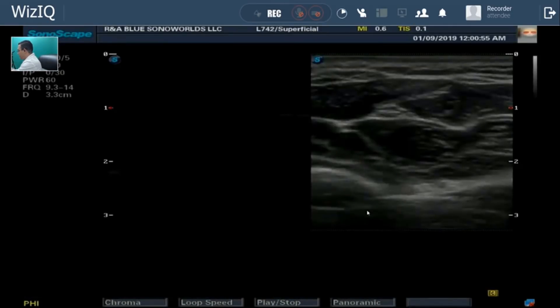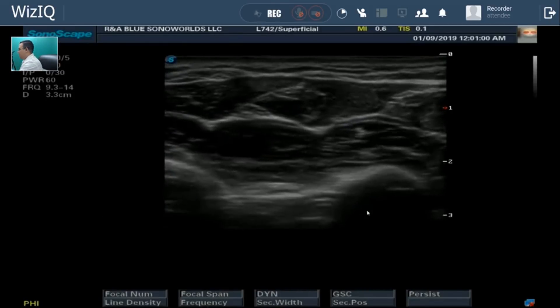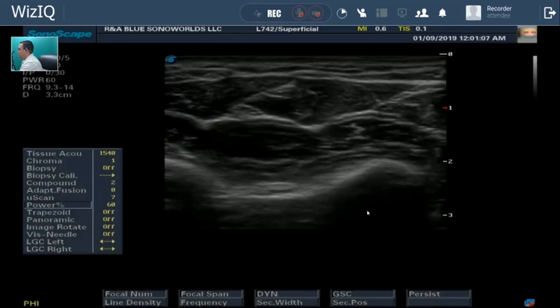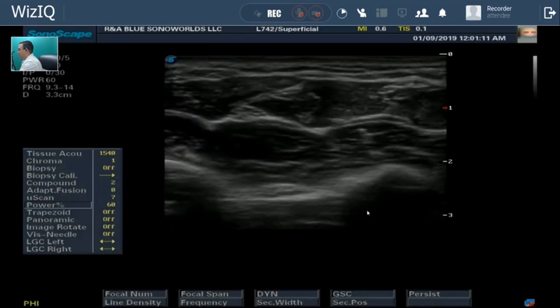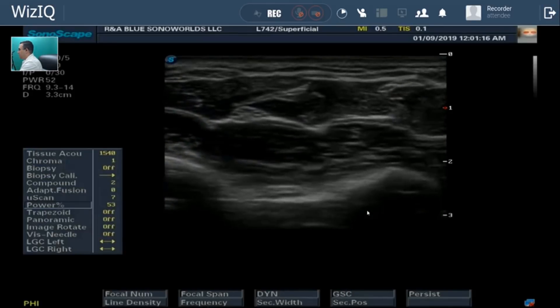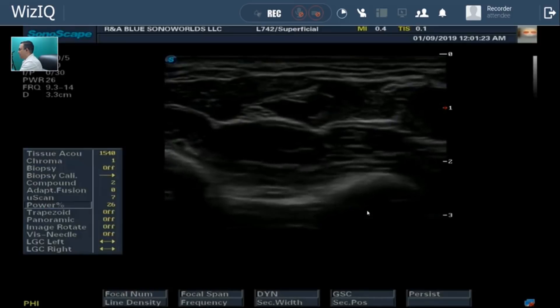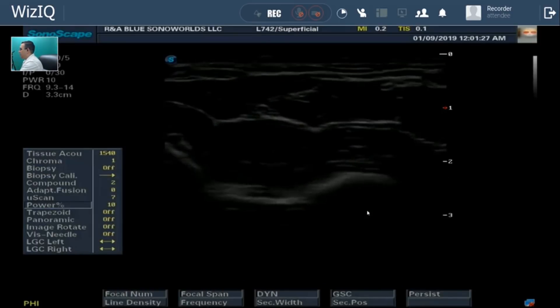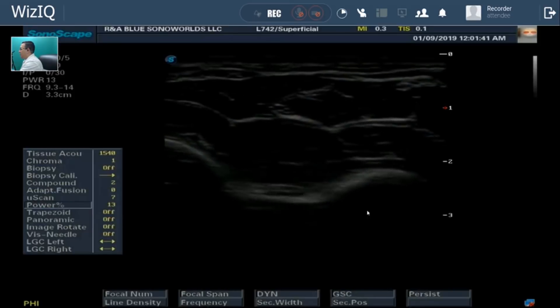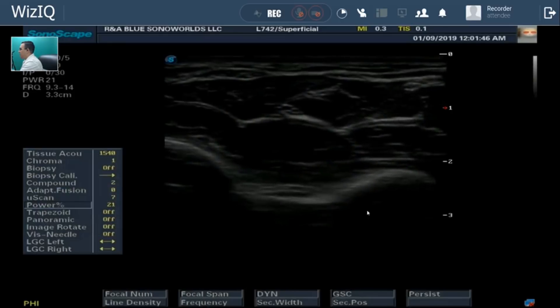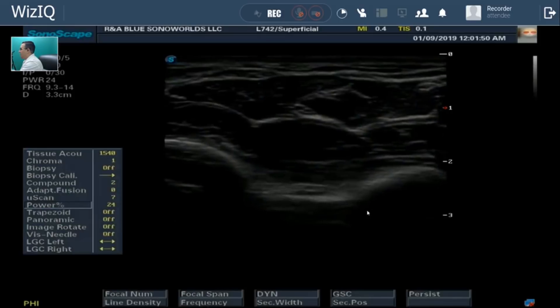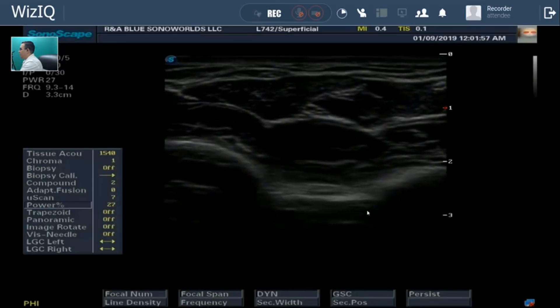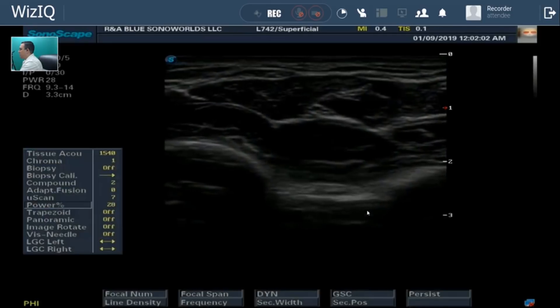So we're live now. I'm going to press here. And can you take a look to the left of my screen in there? Yes. This is power 60%. I'm going to reduce that power. Reduce the power. Reduce the power. More and more. Can you tell me what's going on? Well, the image is getting dark. The image is getting darker. Yes. It makes sense. And when I increase the power, then the image is just getting brighter. You know, the overall gain makes the same thing, right? The overall gain makes the same thing. It's just that the power makes it in transmission. And the overall gain makes the same in reception. The power is the function of the pulser and the overall gain is the function of the receiver.